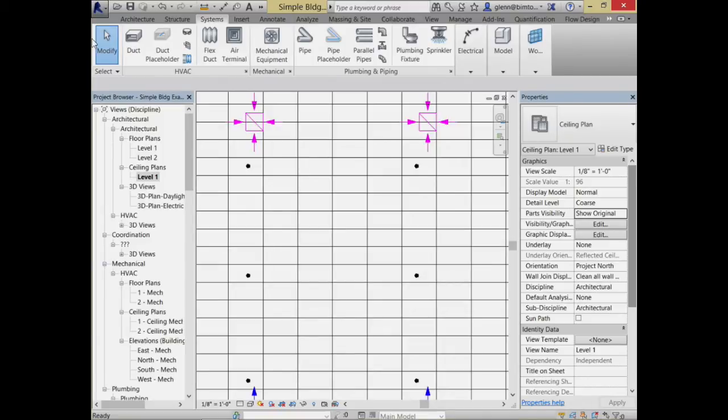I always think of them being, let's say, every 15 feet away from each other, center to center or something like that. Yeah, because even in here, there's one over there, one over here, one over here. So that's kind of about right. A lot of it has to do with what the interferences are. For this room, there's 6 sprinklers that I can see. If I'm counting 2, 4, 6, 8, 10, 12, about 16 feet away, and that's probably pretty close.